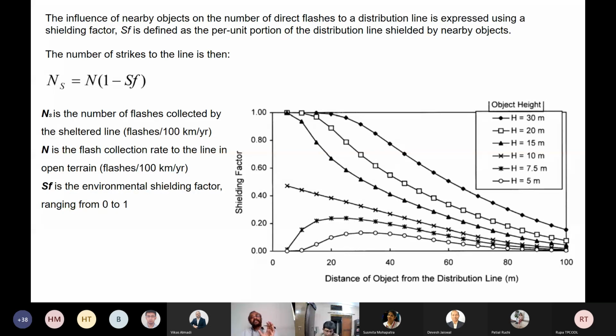However, as these medium voltage and transmission lines are running in the deserts where there are no other objects in the vicinity, the line is the only protrusion for a large area, so most of the lightning coming to ground terminates at the medium voltage or transmission line of the area. So that is one reason. Apart from that, there was another reason: the ground conductivity of the area was extremely poor. These two mattered in causing very high lightning damage to the pole-mounted transformers.